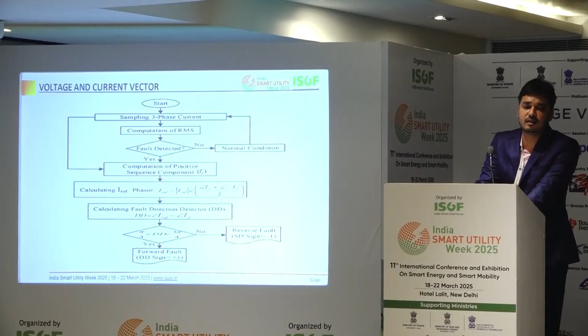If the fault is within this range, it is a forward fault, as usual in the radial network. But for the reversal case, if the angle is not between these two angles, that is a reverse fault. So we can measure the direction of this reverse fault, and we will separate these lines.